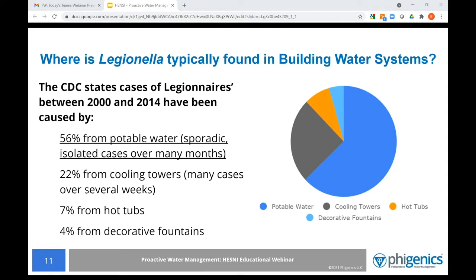We next wanted to share where Legionella is typically found in a building water system. I think this is interesting because most people hear about Legionella from the large cooling tower outbreaks where a lot of people get sick at once. But the data shows that most cases are caused from the potable water system. And these are typically sporadic and spread out over many months. In addition to your potable water system and your cooling towers, some other water systems of concern are hot tubs and decorative fountains.